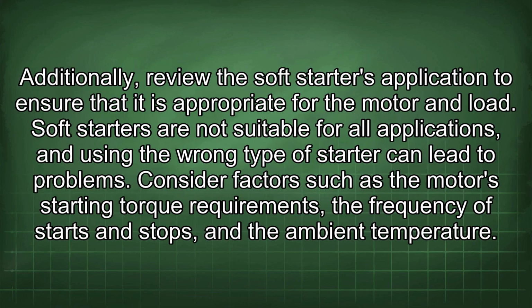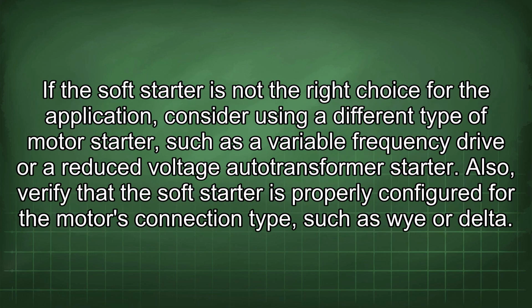Additionally, review the soft starter's application to ensure that it is appropriate for the motor and load. Soft starters are not suitable for all applications, and using the wrong type of starter can lead to problems. Consider factors such as the motor's starting torque requirements, the frequency of starts and stops, and the ambient temperature. If the soft starter is not the right choice for the application, consider using a different type of motor starter, such as a variable frequency drive or a reduced voltage auto transformer starter.